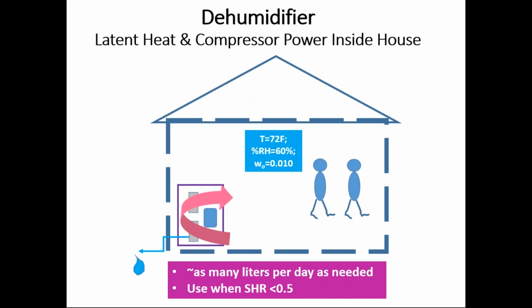And then finally, a dehumidifier can remove as much water as you want. You just buy the capacity you want. The important thing to note is that a dehumidifier is all contained within the house. And so the heat that's removed from the water vapor to condense it into a liquid, and the power to run the compressor, are rejected internally inside the house instead of outside the house, as in the heat pump and the smart ventilator. So this heat has to be removed by the air conditioner in the house.